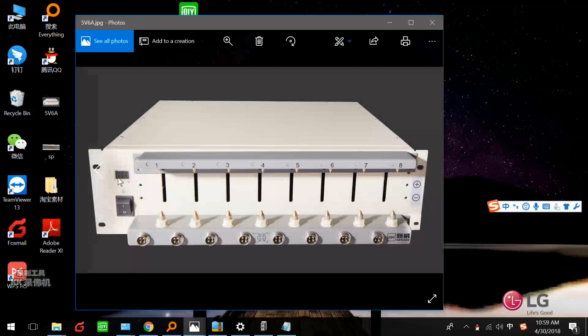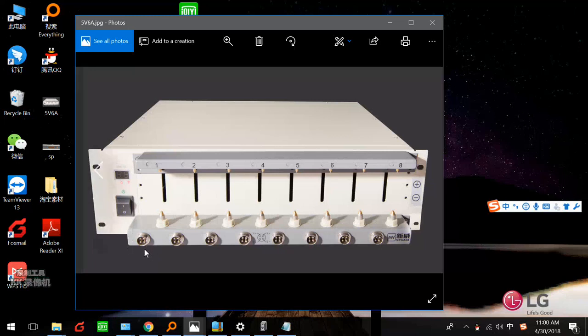First, the hardware connection. Here I have a sample — it is our most normal battery testing system, 5V6A. This is our unit ID, meaning device ID. Switch on the power first. The battery holder here is for cylindrical batteries like the 18650. The upper side is positive and the lower is negative — don't connect negative to positive. There is also a universal port with cables for polymer or prismatic batteries. You can only use one at a time — either the pin holder or the universal port, not both together.